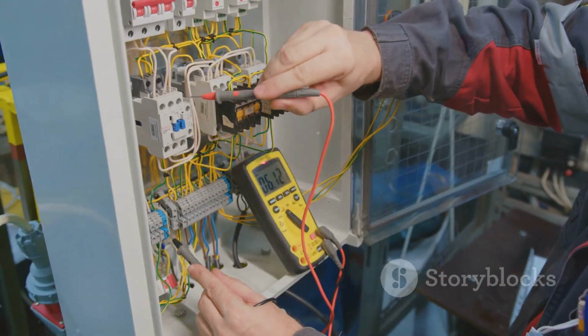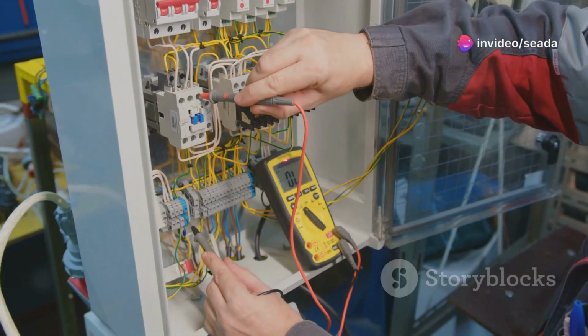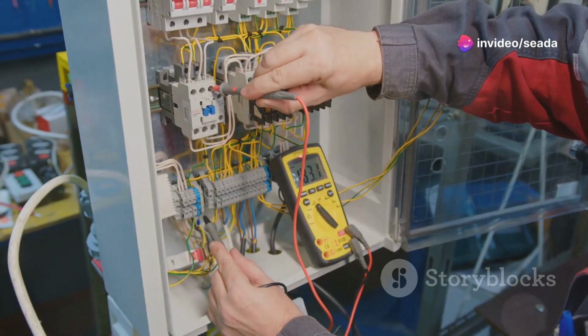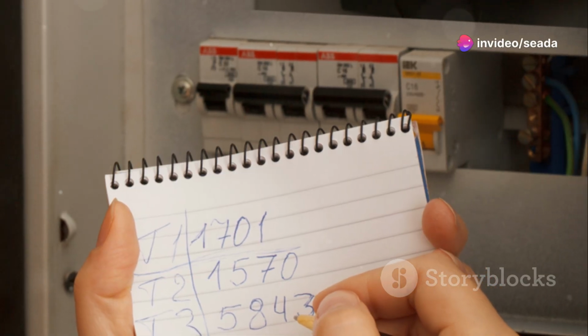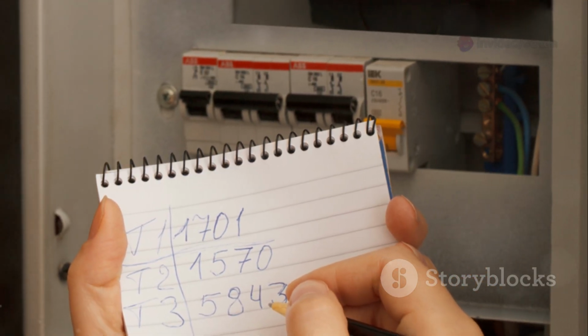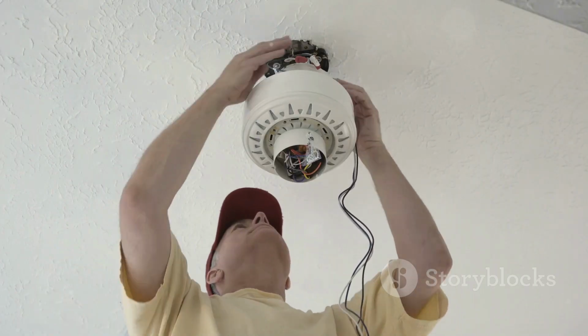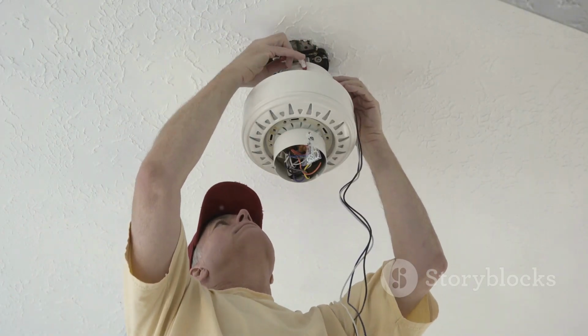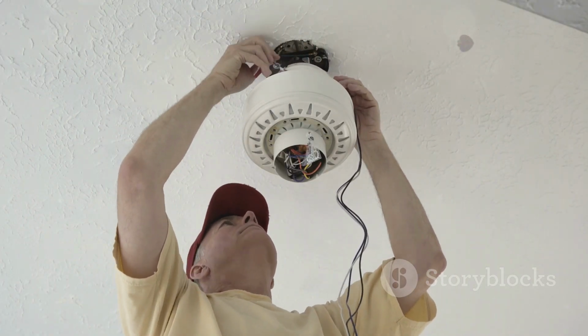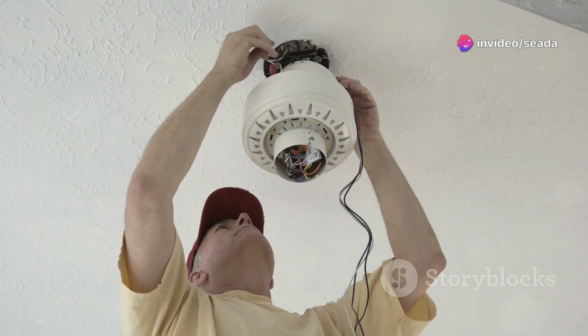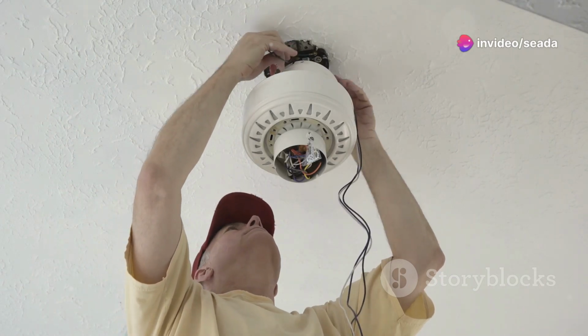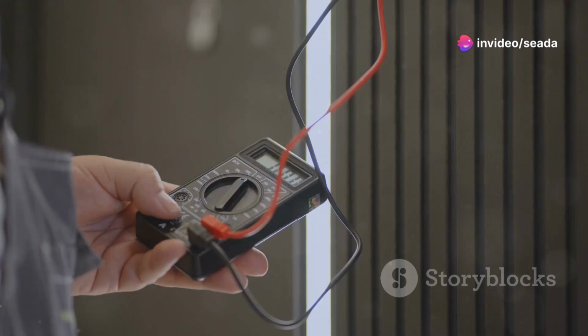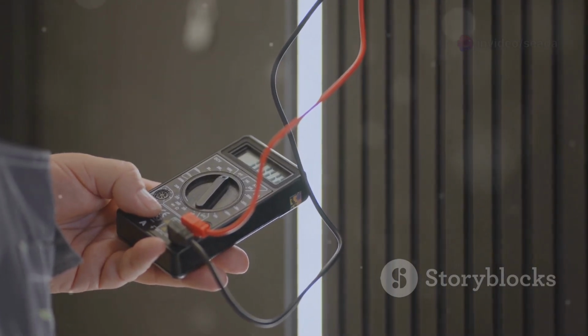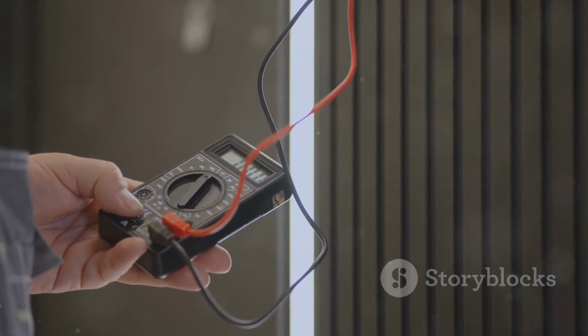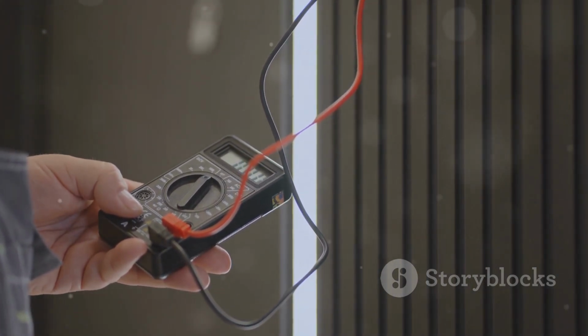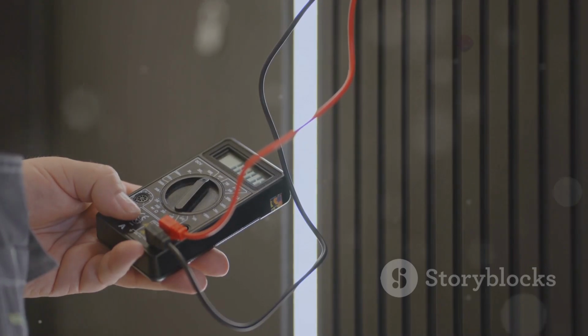If not, the problem may be a faulty MCB or a break elsewhere. Sometimes the issue is hidden deeper in the wiring or the breaker itself. To find a short, disconnect fittings one by one and retest until the fault disappears. This helps you narrow down the exact location of the problem. This process of elimination isolates the problem area. Take your time and work methodically for the best results.